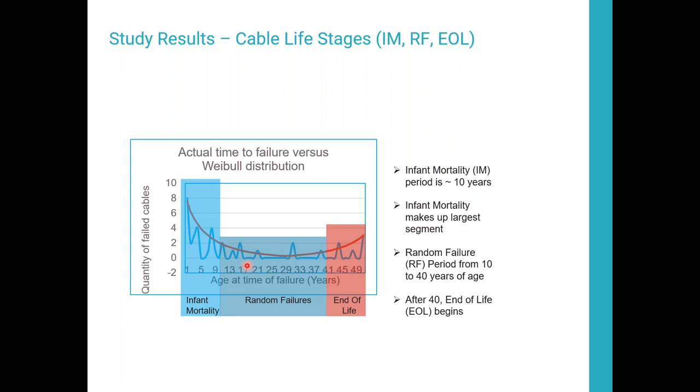And what we found doing some different studies, and we've done a couple of papers on this, is that we get a lot of early life failures on cables. A lot of times it's workmanship issues where the terminations are done improperly, and they cause failures within the first couple of years. And it's a significant problem because people have the appearance of, well, it's all brand new equipment, I don't have to worry about it for a while, and then they have failures happen.